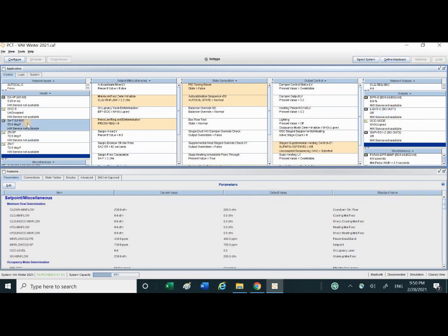Supply air temperature, this is the RTD, default value is 55 Fahrenheit, and this one is the room temperature set point. Default value is 72, and the room temperature is what the thermostat senses. If the set point is equal to or lower than the room zone temperature, then the output heating is off. It's off. So these are all inputs and these are all outputs. Now we simulate and we manually change these values and then see what the output is.